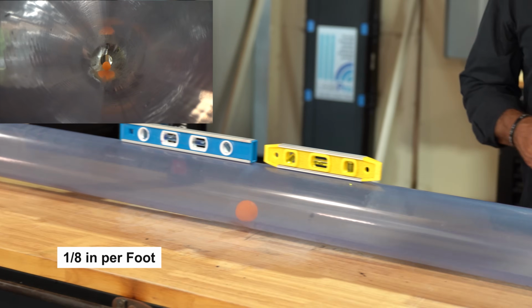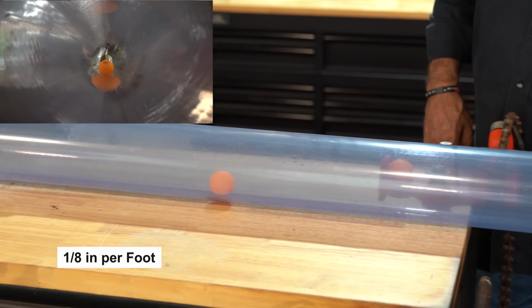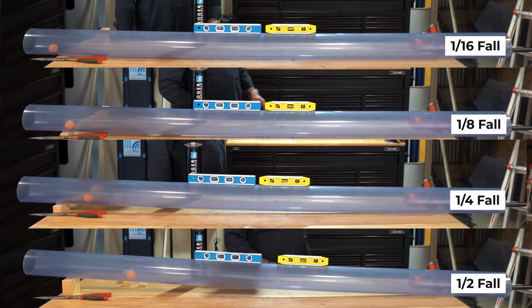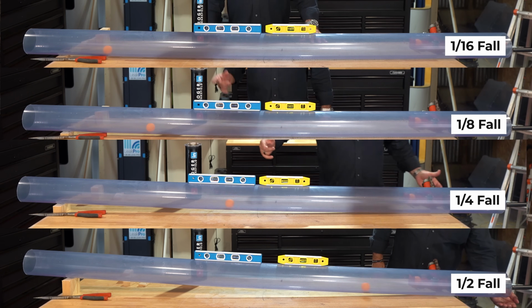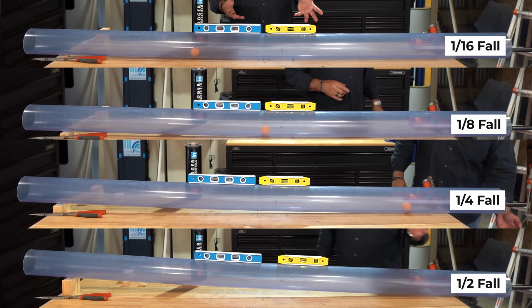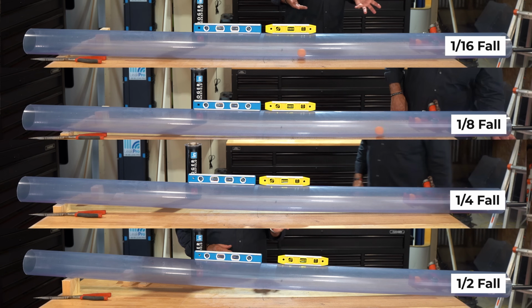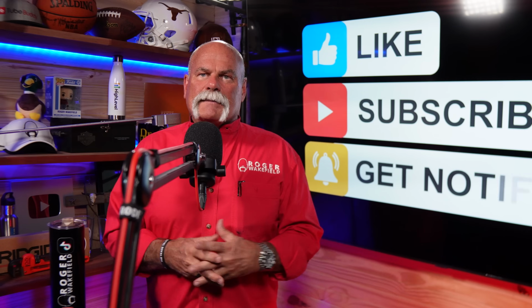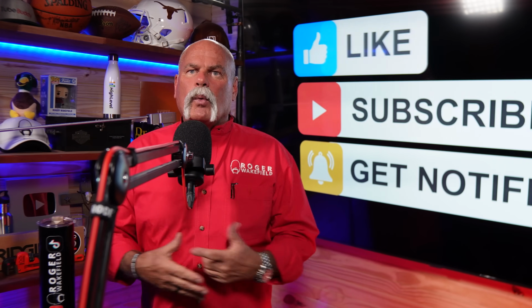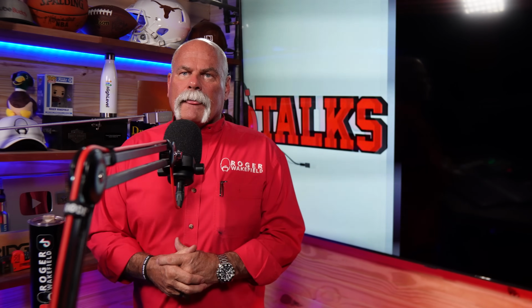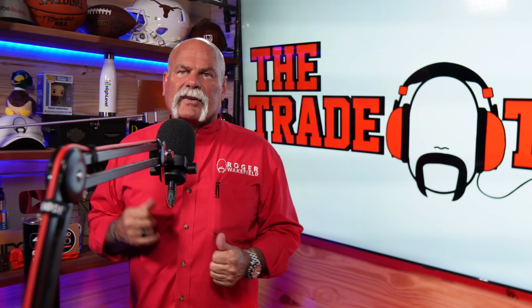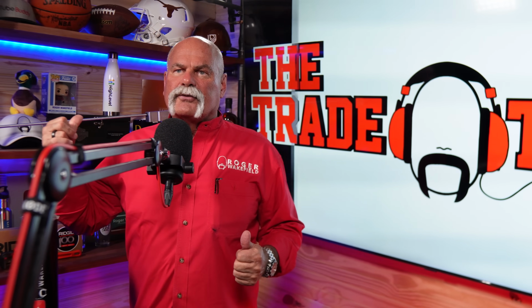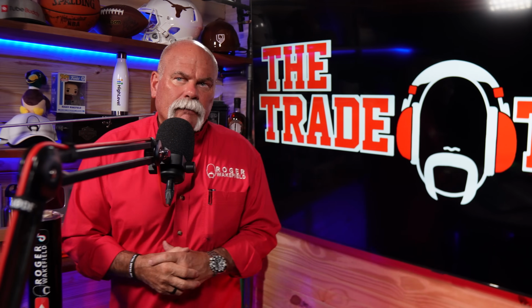Drain lines that don't have the correct slope can lead to clogs and poor drainage. Code typically requires a 1/4 inch per foot slope for proper flow. Now, this is funny. I remember one of the first times that I was running a project and went out for the inspection, and I hollered at my apprentice, I said, look, go to the trailer, get me my 2-foot level.